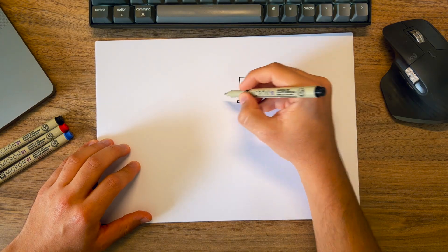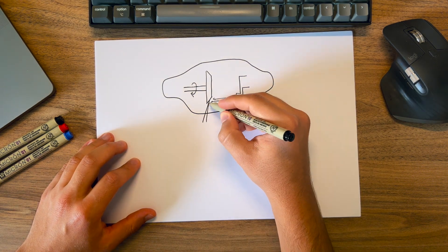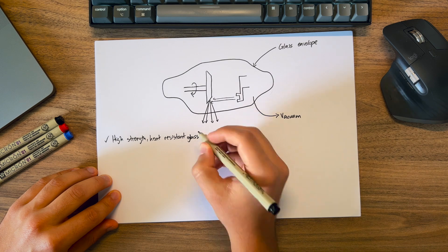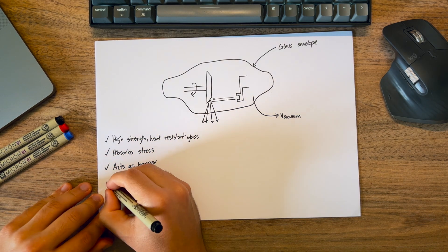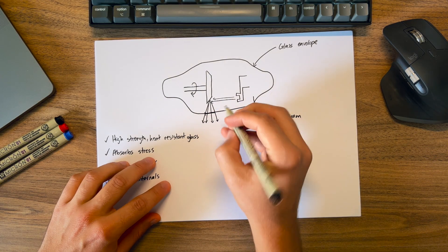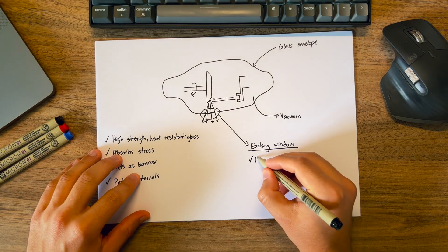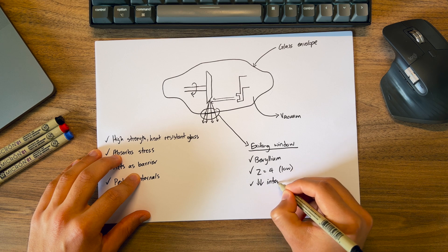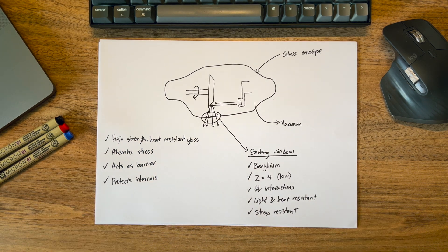All of this is encapsulated by a vacuum sealed glass container. It's this vacuum that allows the electrons to freely move from the cathode to anode without colliding with any air molecules, because if it did, it would cause them to scatter and interfere with the production of x-rays. This glass has to be made of a high strength heat resistant glass that can withstand the stresses inside, and it also acts as a barrier protecting the tube's internal components from contamination. At the bottom of the glass envelope is where you find the exiting window, which is designed to allow the generated x-rays to exit the tube with minimal absorption and scattering. Beryllium is a common material used for the exiting window because it has a low atomic number of 4, meaning fewer electrons and less absorption of x-rays, and it's also lightweight with a high melting point.